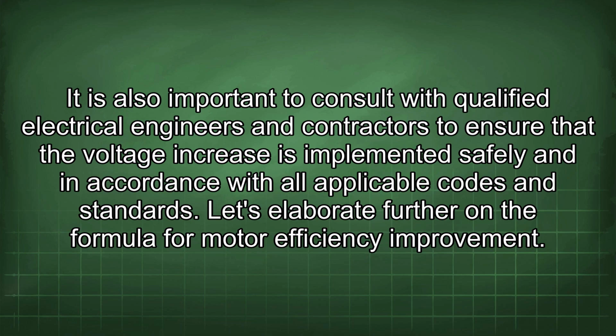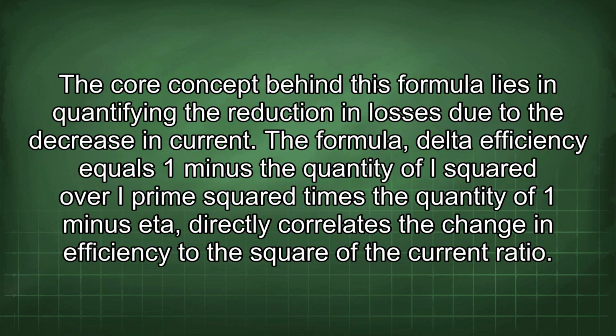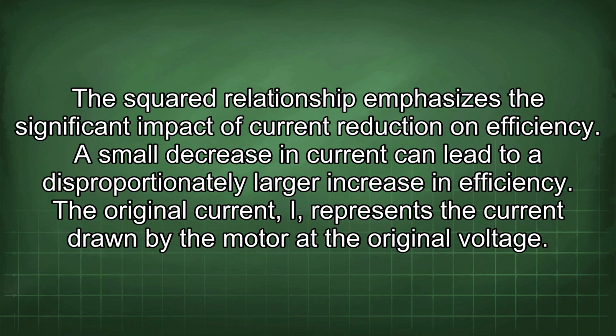Let's elaborate further on the formula for motor efficiency improvement. The core concept behind this formula lies in quantifying the reduction in losses due to the decrease in current. The formula, delta efficiency equals 1 minus the quantity of I squared over I prime squared times the quantity of 1 minus eta, directly correlates the change in efficiency to the square of the current ratio. The squared relationship emphasizes the significant impact of current reduction on efficiency. A small decrease in current can lead to a disproportionately larger increase in efficiency.